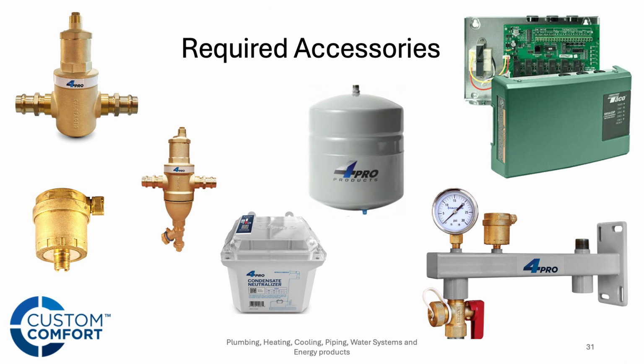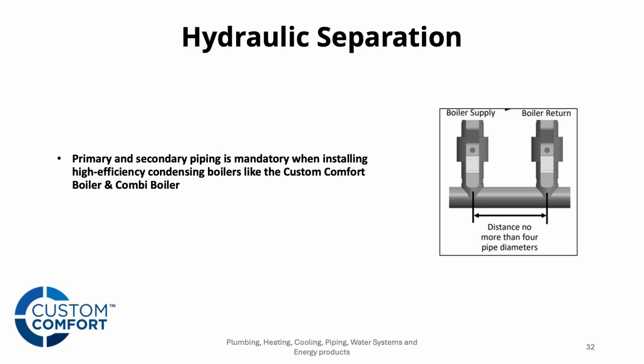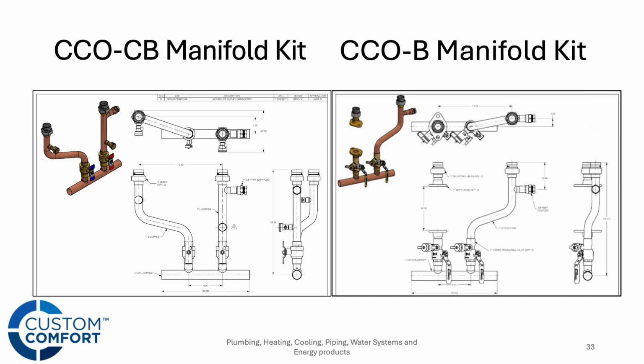But then let's talk about a few more things that go with the boilers, right? A couple of things on both the heat only and the combi that we talked about tonight. These are going to require some type of hydraulic separation, right? At the end of the day, we don't necessarily care how you make that hydraulic separation, whether it be closely spaced tees, a hydraulic separator, or one of our custom comfort manifold kits. So we've got the combi manifold kit on the left, then the heat only manifold kit on the right. You'll notice the big difference between the two there.